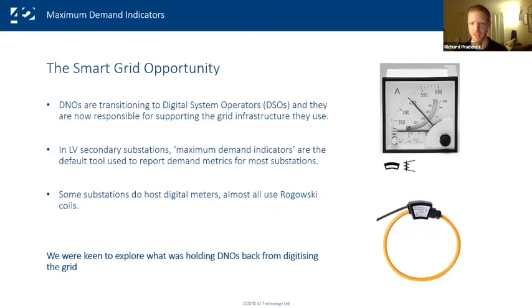It may have happened because feeders were switched in and out further up the network, or load was incorrectly routed through the substation and then rerouted. But according to this meter, you'd have a maximum apparent demand value, and that would trigger investment decisions about whether to upgrade the substation, add more feeders, or replace it with something newer.